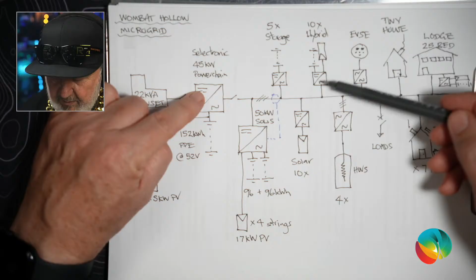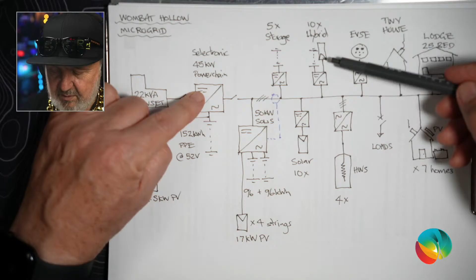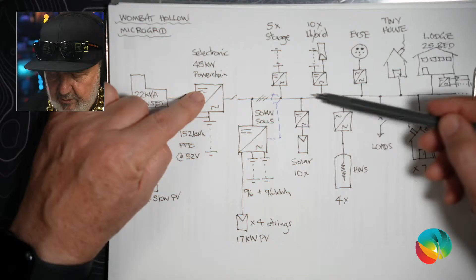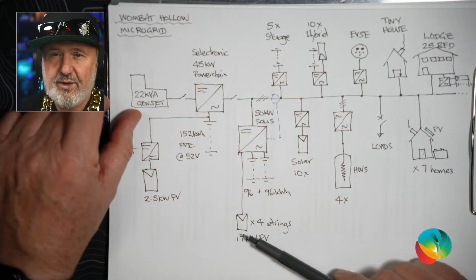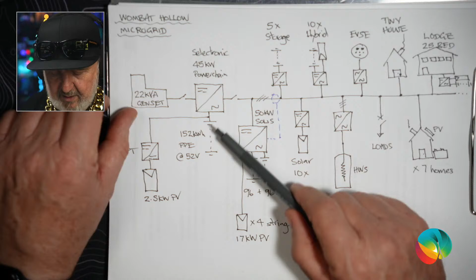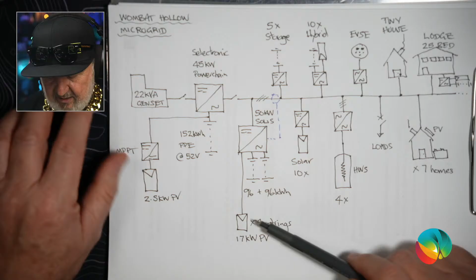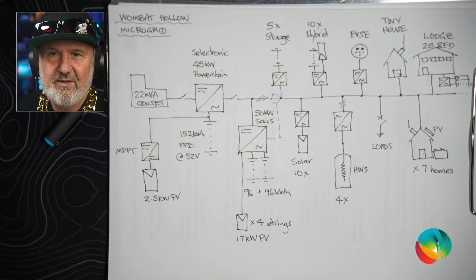The other benefit too is you might notice I've got a bunch of other systems here that are generating sources. So I've got like 10 solar inverters, different brands, 10 hybrids, some storage inverters, etc. These will be generating as well, so we'll get some power flowing back towards the power chain. So we've programmed the Solis inverter to take its own solar and export the first 10 kilowatts back to the grid forming system to keep this battery topped up. And then anything over 10 kilowatts coming off its own 68 kilowatt array will then support the loads and charge the batteries. And that's quite a complex set of things.